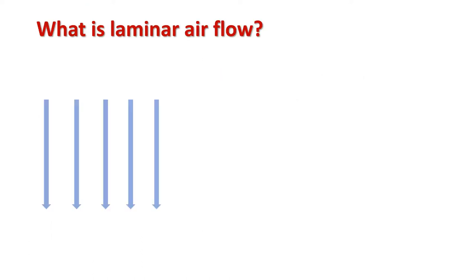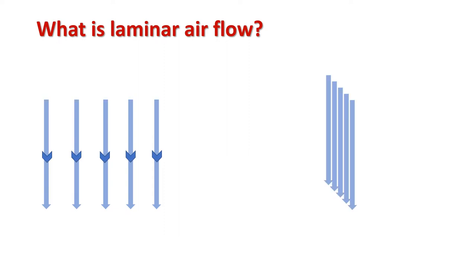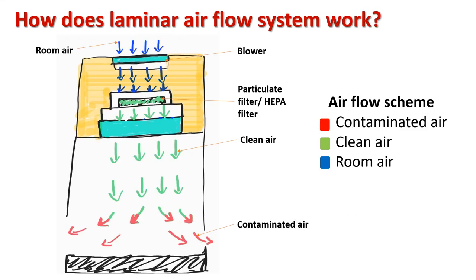Laminar airflow system allows travel of gas molecules in multiple straight lines which are parallel to each other. These layers of gas molecules are uniform in velocity and do not mix up with each other. This provides a highly efficient circulation system which captures and eliminates all sorts of impure particles present in the air and maintains a clean and sterile environment.